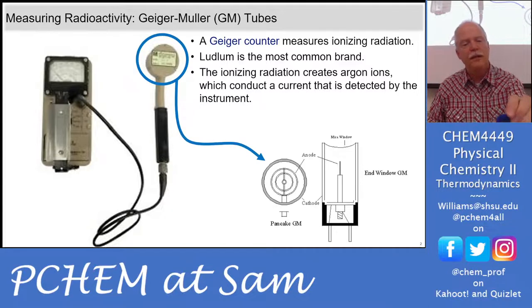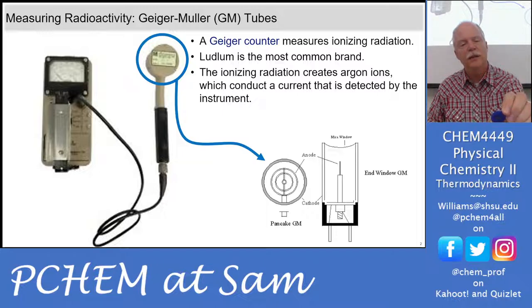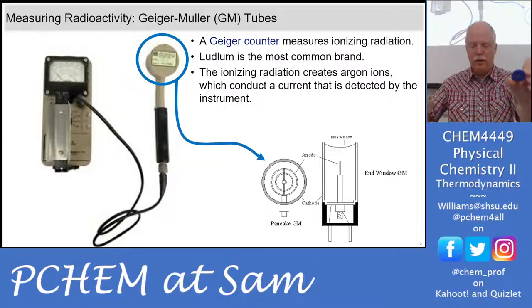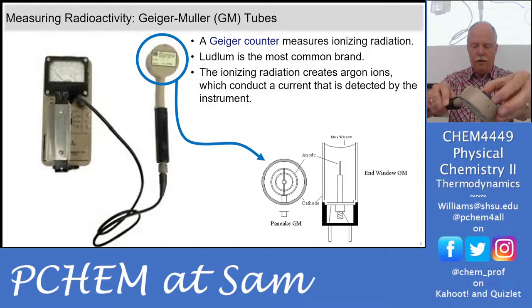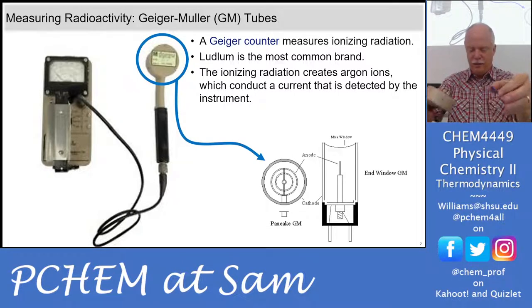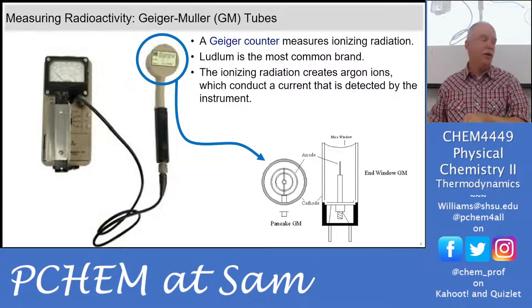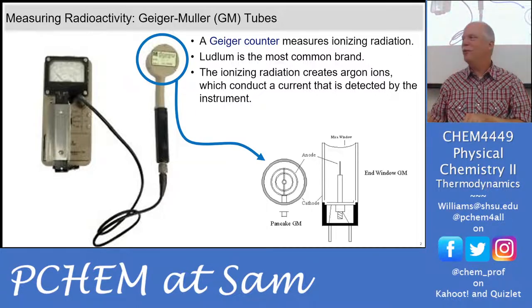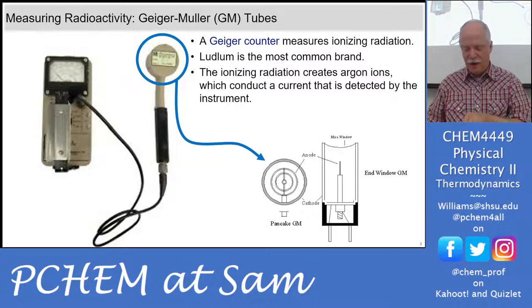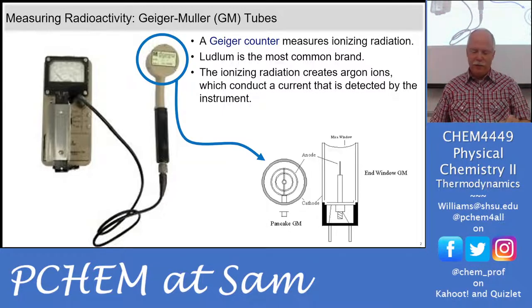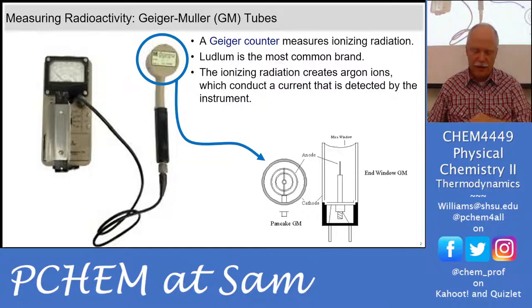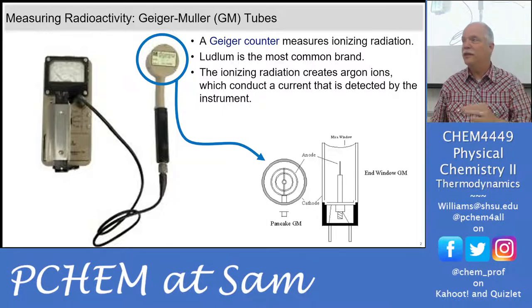This one is cesium-137 — one microcurie, February 2008 — and it has a half-life of 30 years, so there should still be some beta particles coming off it. It's giving me counts, and it's showing a high alarm — it says that's very radioactive for this probe. It has a low alarm and a high alarm: if you're checking your shoes and don't see any counts or alarms on the low, you're clean and can leave the facility.